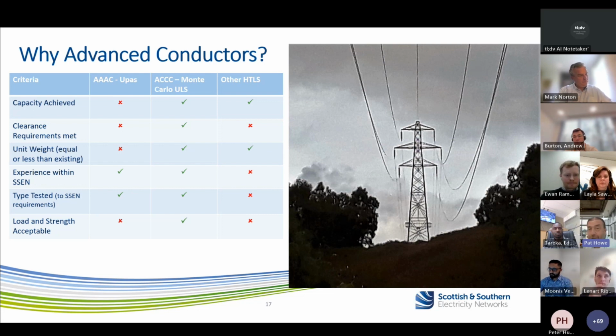What I'd like to bring your attention to is the picture on the right. I haven't faked this - I'm not technical enough to do it even if I wanted to. On the left is the new Monte Carlo conductor, and on the right is the old Lynx conductor. I know it looks like the one on the right was pulled up by hand because it sags so badly, but genuinely that is the difference in profile between the two conductors, and it gives you some idea of the benefits. Bear in mind, with the one on the left, we've also doubled the capacity of the line on the existing towers.